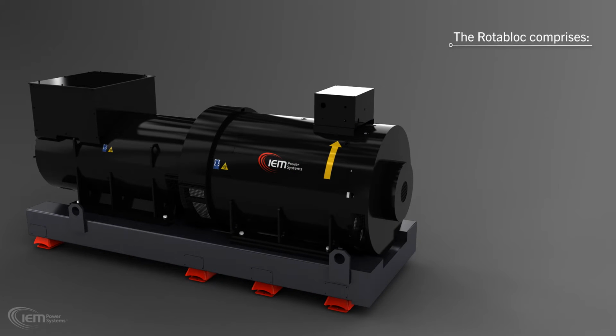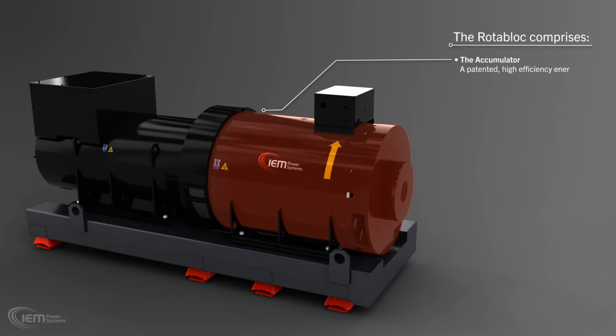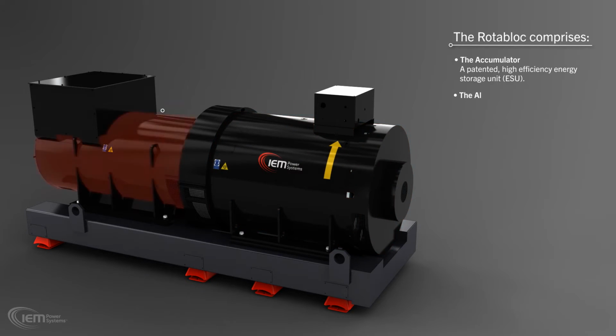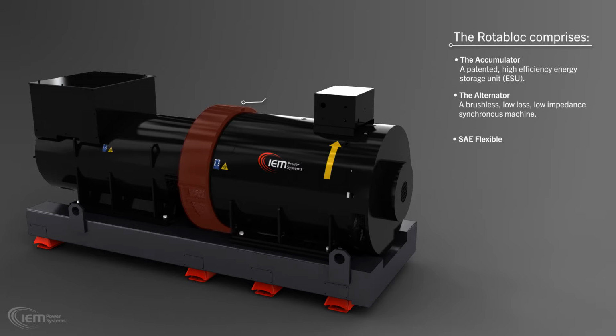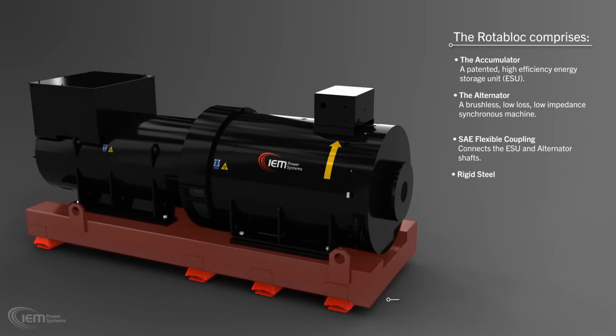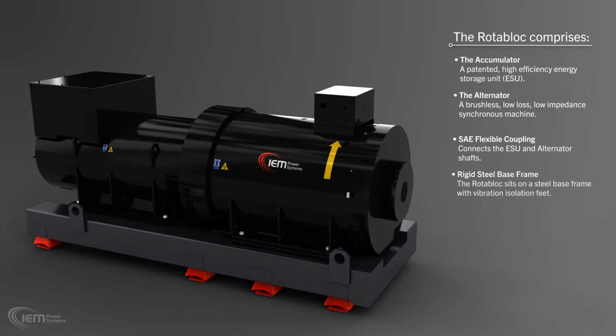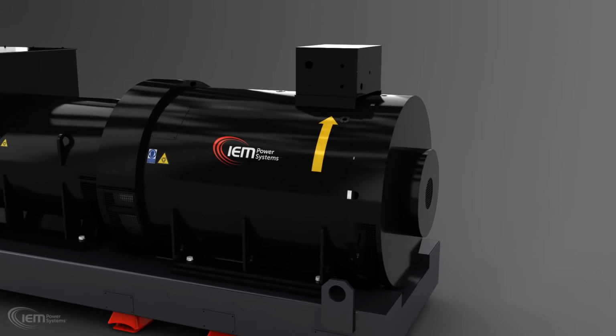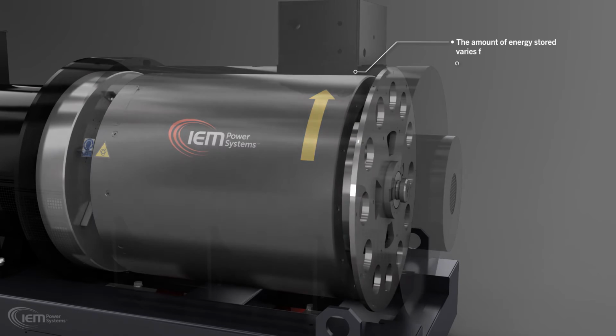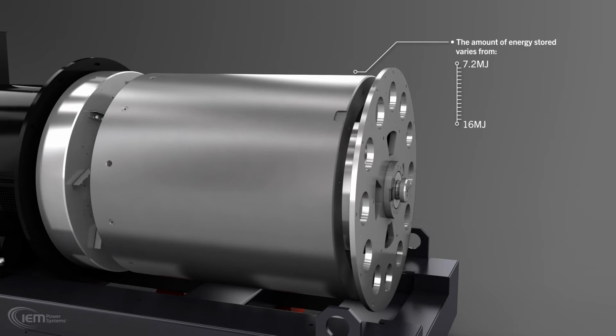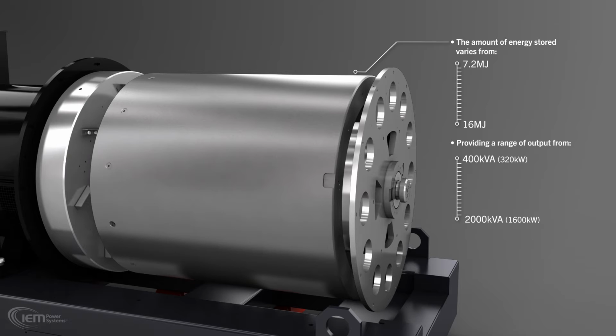The Rotabloc comprises a patented high-efficiency energy storage unit, the accumulator, and a brushless, low-loss, low-impedance, synchronous machine, the alternator. The flexible SAE coupling connects the ESU and alternator shafts. The Rotabloc itself sits on a rigid steel base frame with vibration isolation feet. The Rotabloc stores energy efficiently in a rotating steel drum. The amount stored varies from 7.2 megajoules to 16 megajoules, providing a range of outputs from 400 kVA, 320 kilowatts, to 2000 kVA, 1600 kilowatts.